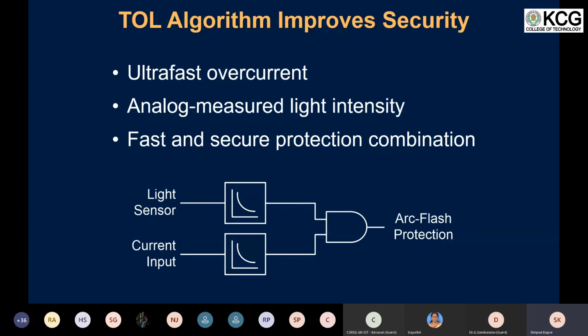So basically, we know that to convert any analog signals to digital, you would require A to D conversion, and then you do a filtering. This filtering could be based on the full cosine filter, but the disadvantage with the full cosine filter is that it is going to take one cycle to capture a cycle. That is, in order to measure the quantities associated with one cycle, there is a delay of one cycle that is going to occur. So here we are going to eliminate those delays. Since we are not looking at the full cosine filter, we are going to use a much faster filter like a half cosine filter in order to measure the overcurrent.